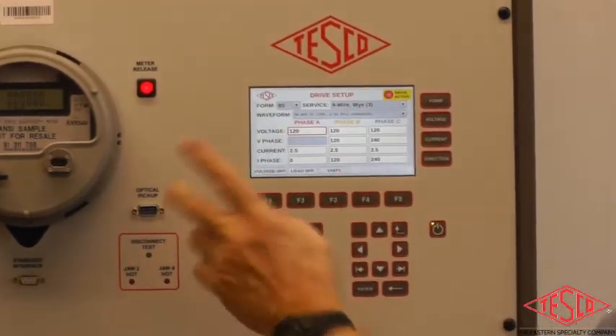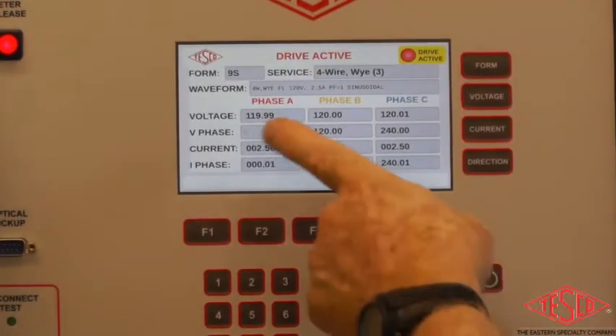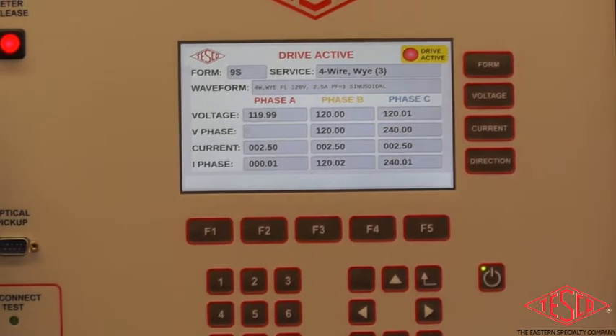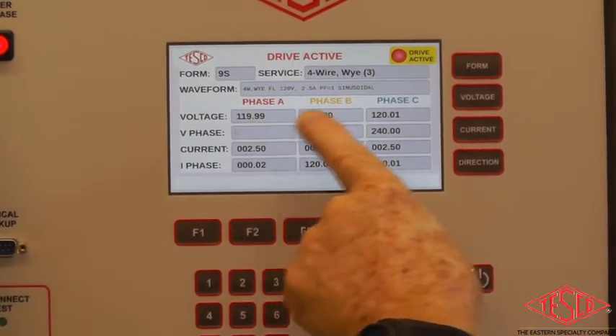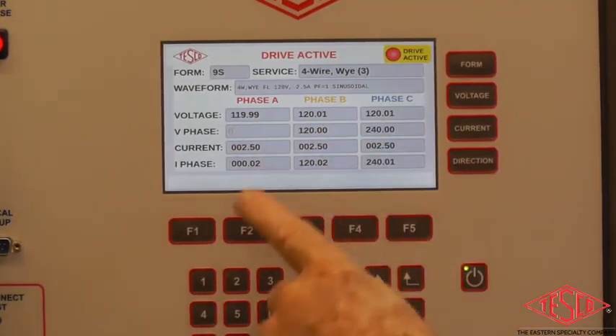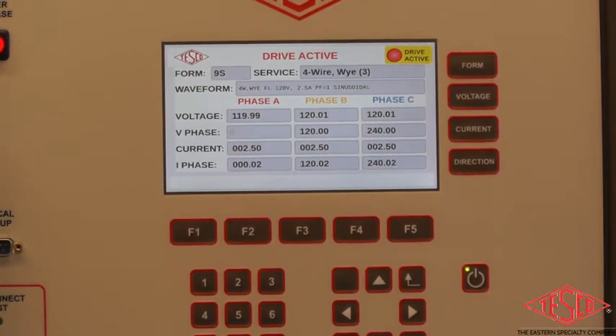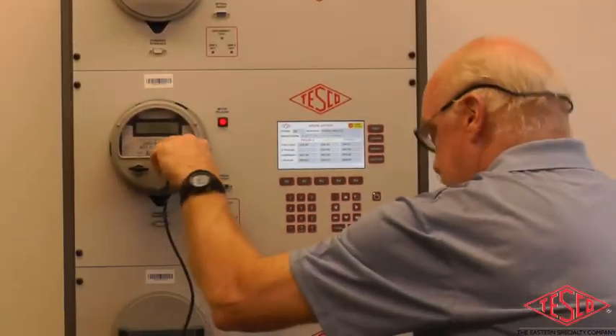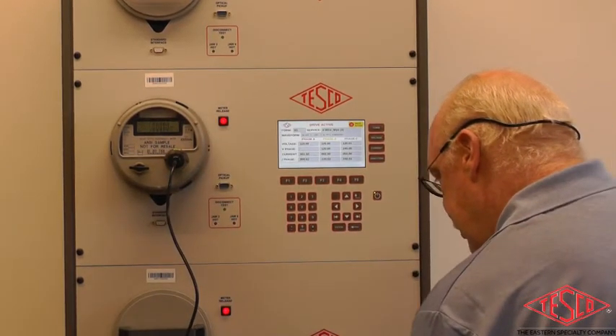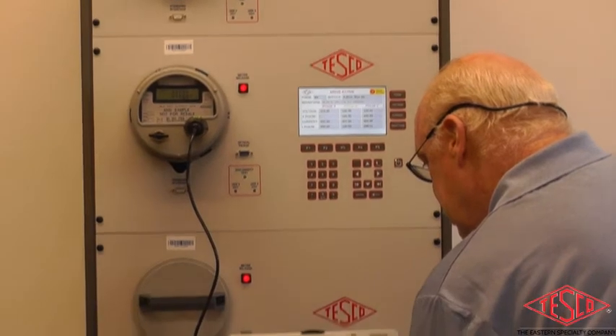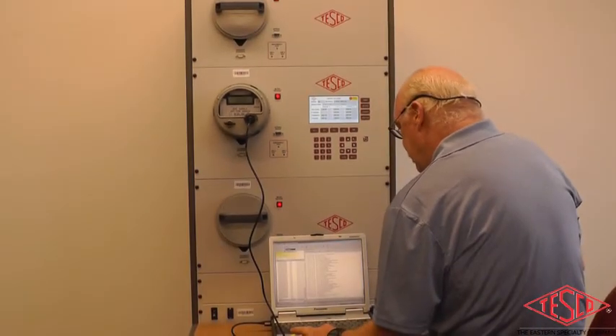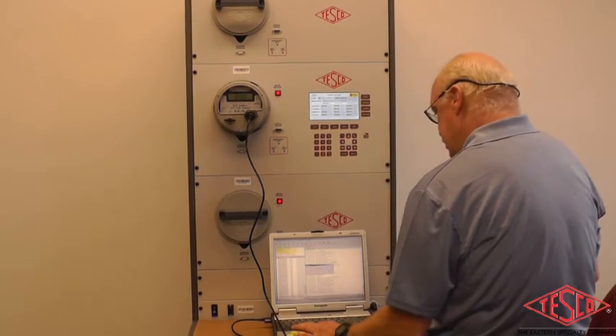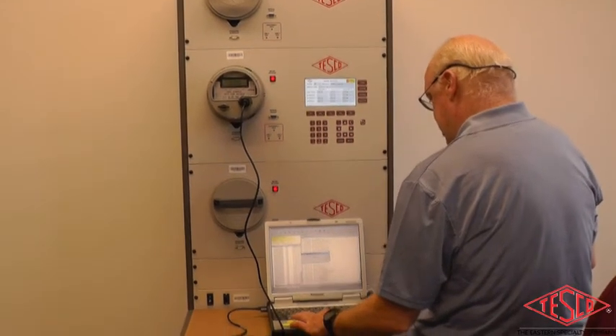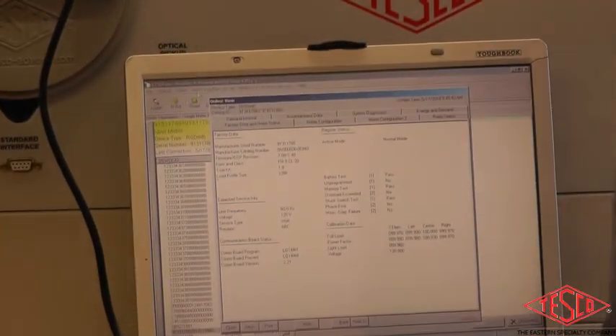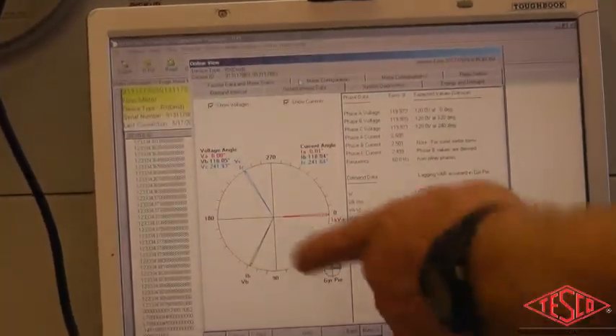So in order to view the active readings, you can press the stats key, and it'll show you actively what is present on each stator. There you have the 119, 120, 120.1, all your currents, and the various phase angle relationships. So I will show you basically how to actually see what the meter is reading. We have a 32 com here, and I'm going to pull up the meter vectors, phasors, they actually call them, and we will be able to see instantaneously what the meter is saying.